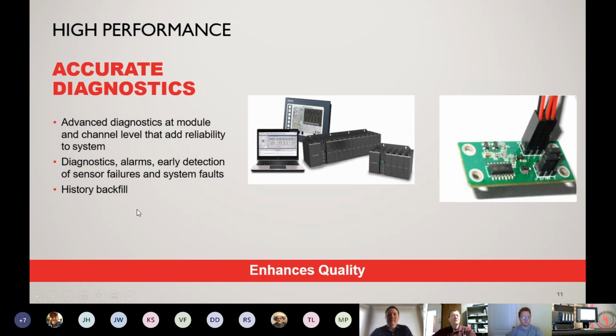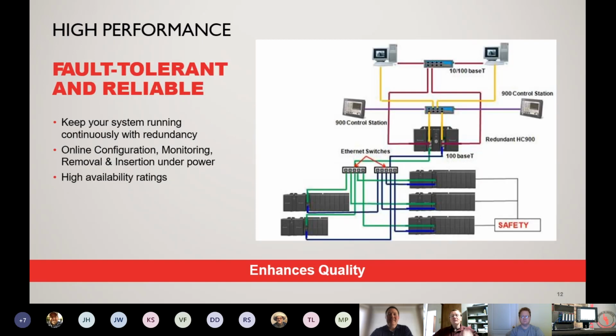The other real big thing that it offers is a history backfill. Let's say, for example, your SCADA system was to go down and come back up after 15 minutes or so. There is a backfill option where the HC900 will take the data that was missing from that point and backfill it into the trend data, so that there's no missing data when you're trying to go back and look for that type of information.